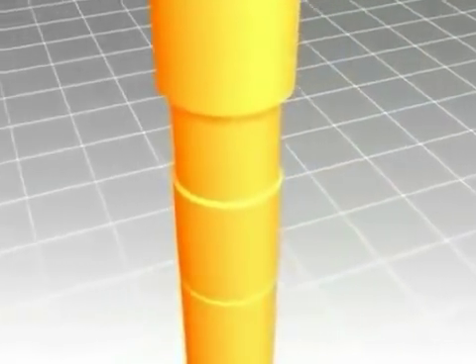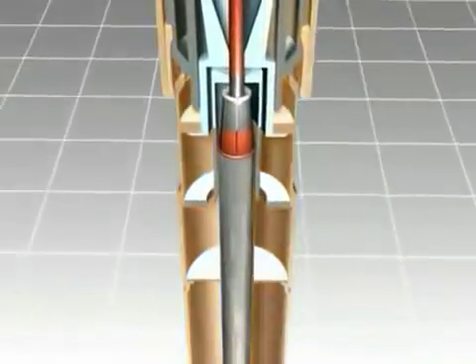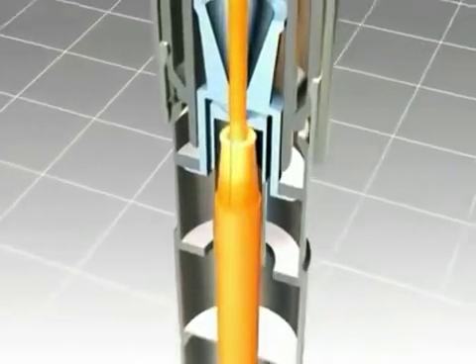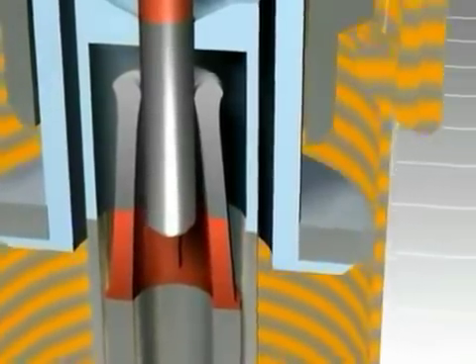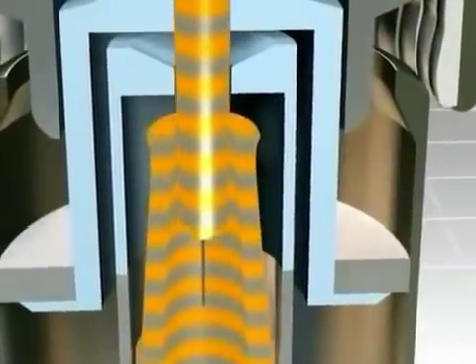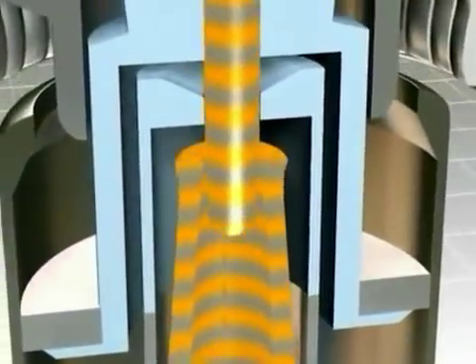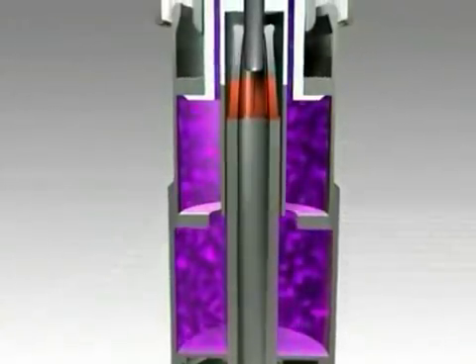During the breaking of operating currents, the main contact opens first, but the current still commutes through the arcing contact, which remains closed at this stage of the switching process. This avoids erosion of the main contact.